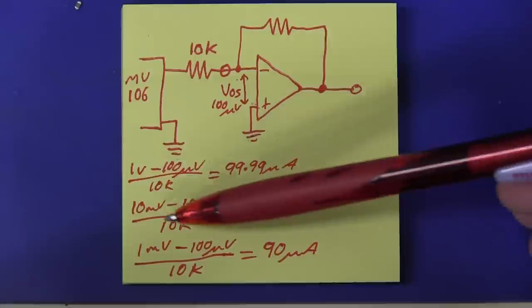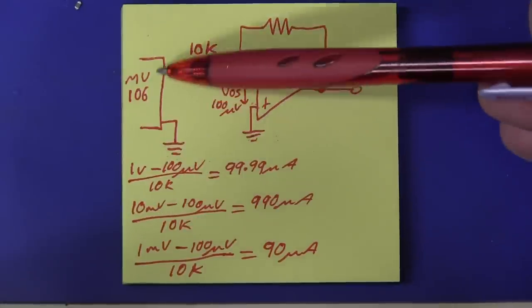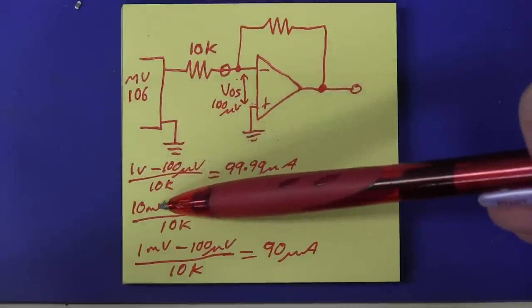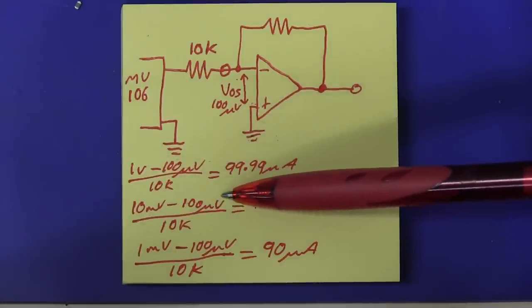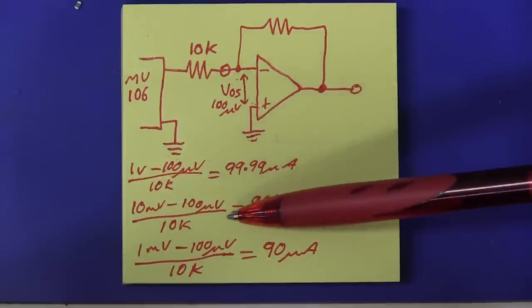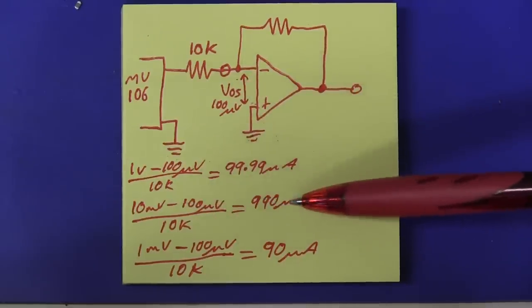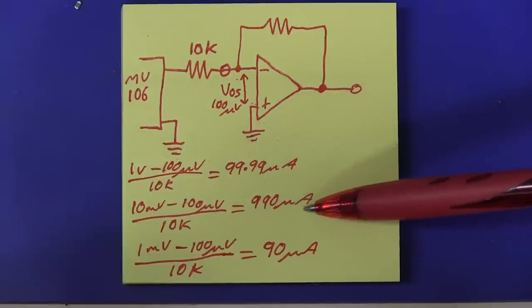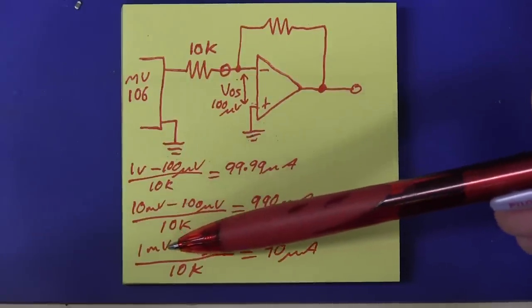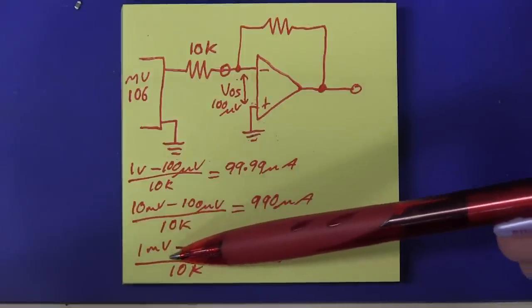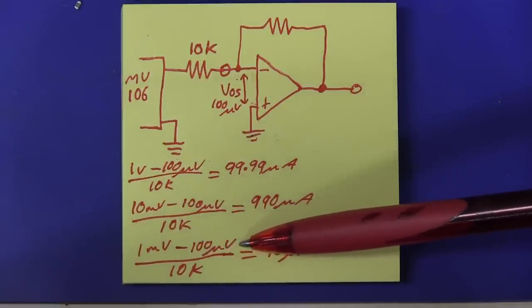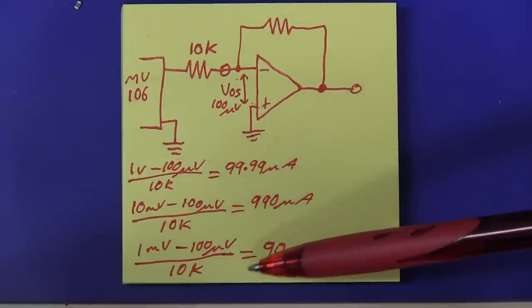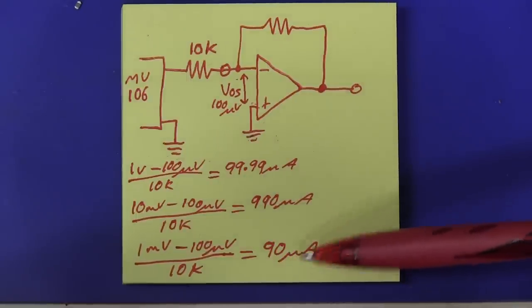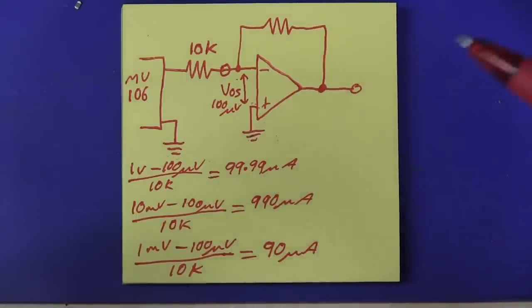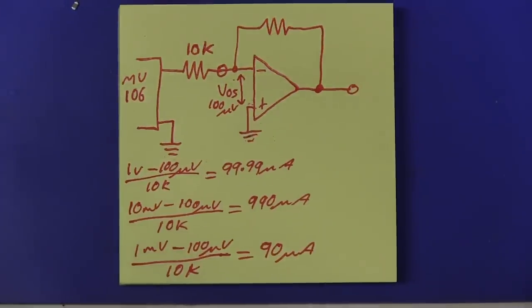It's pretty darn close. But then if we drop our test voltage here from the MV106 to 10 millivolts, then we can see our 100 microvolt offset voltage becomes very significant. You do the math here, and it's 990 microamps. So we'll actually measure that, and we should get roughly that figure. And then if we drop it even further to a ridiculously low voltage, 1 millivolt minus 100 microvolts, of course, that's going to have a very significant error, a 10% error there, of 90 microamps. So let's actually measure that.